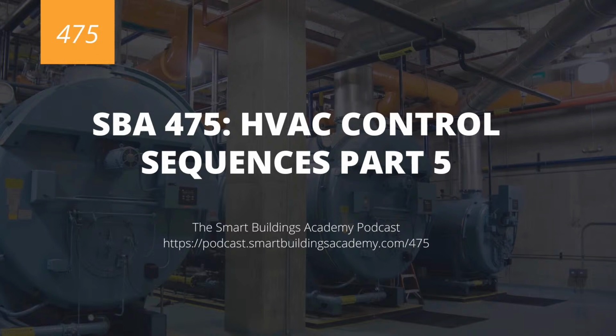Now, here's another thing that you'll see in some hydronic hot water loops that you don't really see in chilled water loops, and this is air dampers being interlocked with operations of boilers, because boilers are utilizing combustion, whereas chillers are utilizing the refrigeration cycle and compressors and evaporators, etc. Boilers are utilizing combustion. What do we need for combustion? In most cases, we need some form of air.